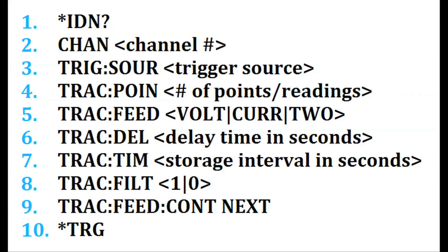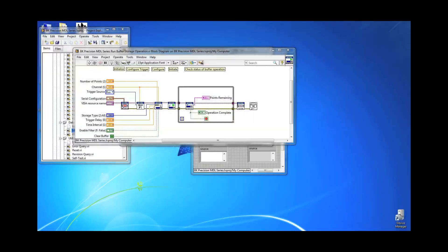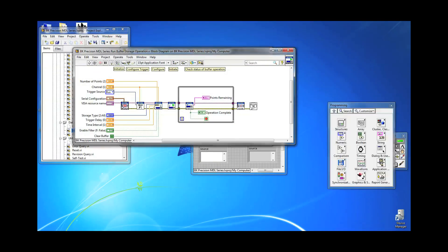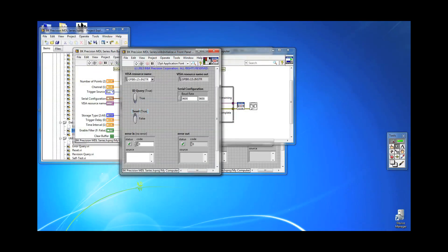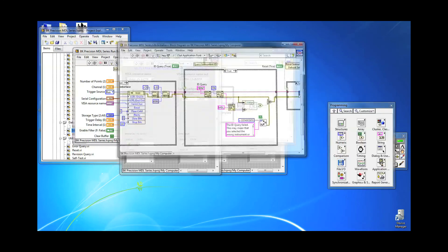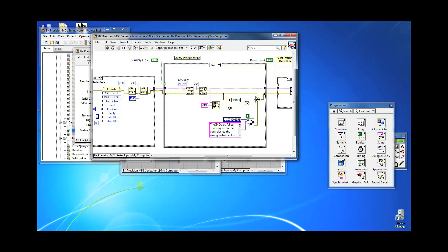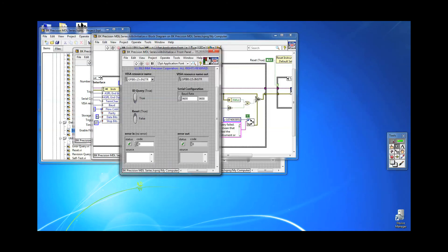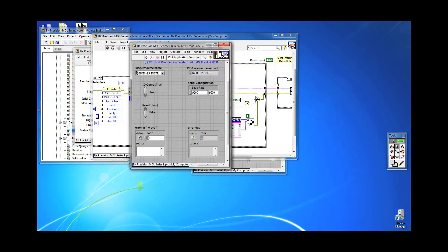Here is the order in which to send the commands, and I will explain each in detail. I have LabVIEW now in front of me and have written a VI for all of the buffer operation commands. So the first command I send is *IDN? query. I have a LabVIEW initialized VI that will send this to query the instrument's ID and check to verify the ID.